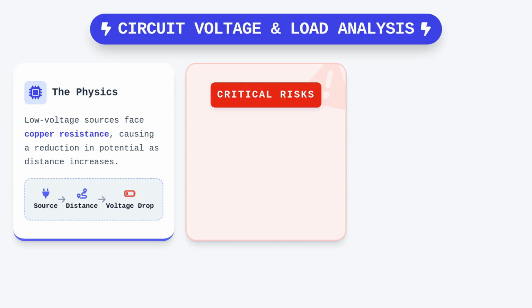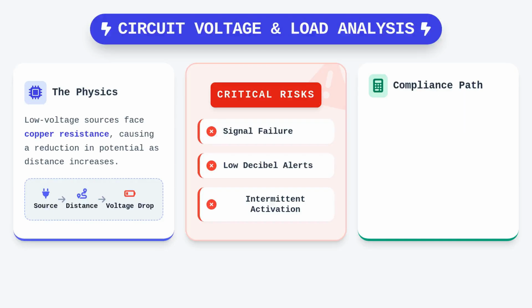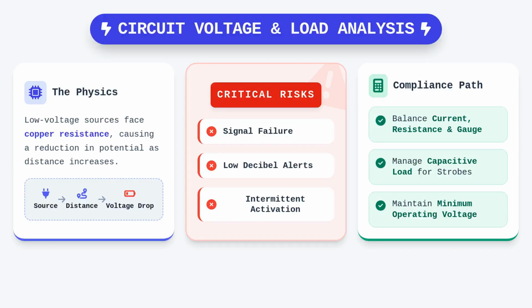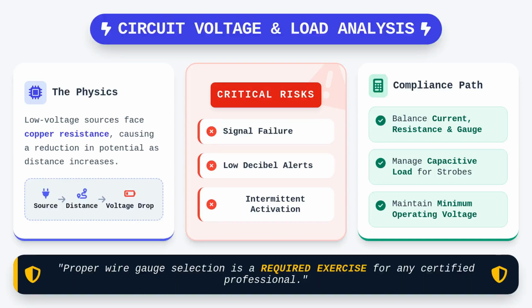If the voltage drops below this threshold, the notification appliance may fail to activate or, worse, provide an intermittent or low decibel alert. Furthermore, when we incorporate strobe lights into these circuits, we must account for the capacitive load they introduce, which can severely distort the electrical pulse if not carefully calculated against the panel's power limits. Proper wire gauge selection is not merely a suggestion, but a required exercise in load balancing for any certified professional.